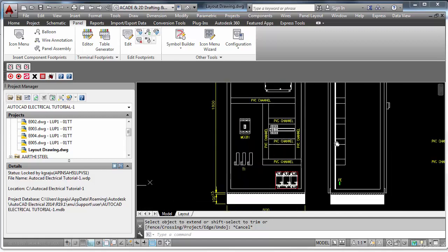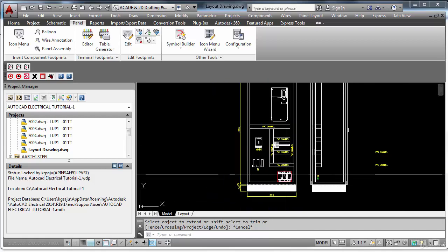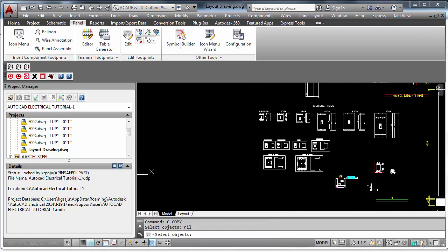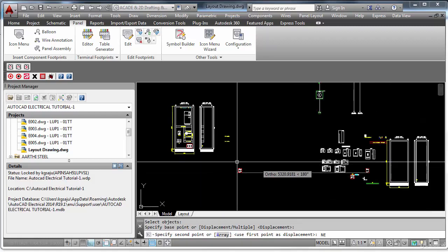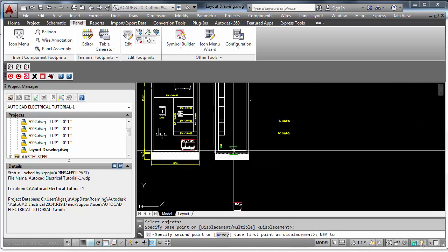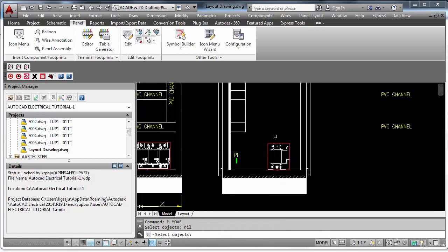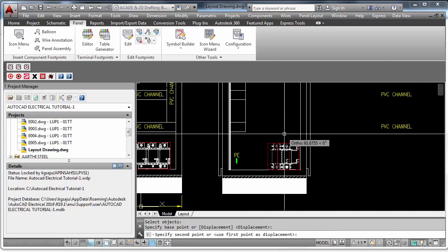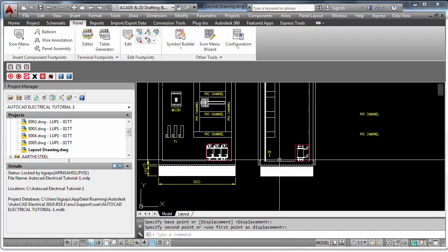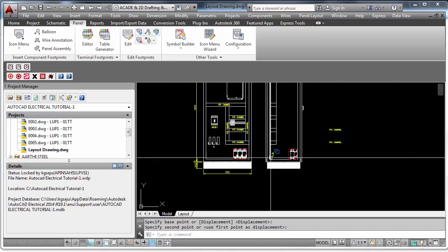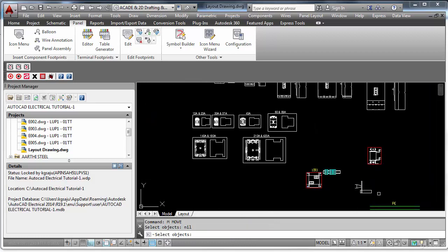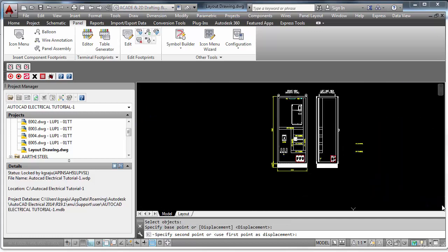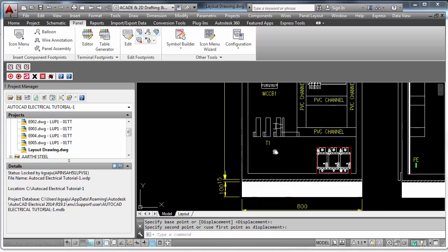You have to visualize the things. I'm looking from the left side view. I'm now viewing from the left side of this panel. So what else will I think? This is overall. Now at the bottom I can see a choke. So I will bring a side view of a choke here. I will keep it somewhat on the front side, because my cable entry is through the bottom. So it won't restrict my gland plates for smooth cable entry.